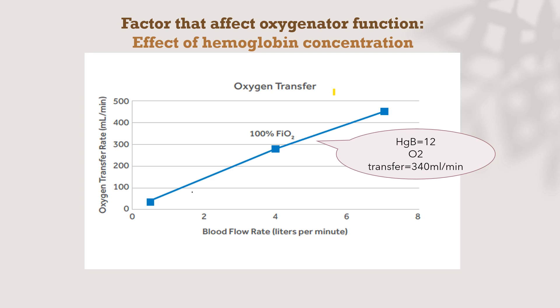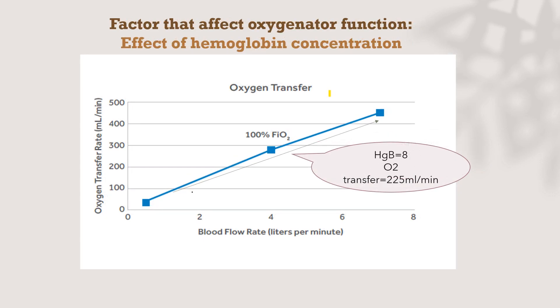Regarding hemoglobin concentration: from this curve, if the patient has a hemoglobin of 12 g/dL, FiO2 100%, and inlet SpO2 of 75%, the oxygen transfer will be 340 mL per minute. But if hemoglobin drops to 8 g/dL with the same flow and same FiO2, the oxygen transfer drops to 225 mL per minute. Hemoglobin plays a very important role in arterial oxygen content through the equation: hemoglobin × 1.34 × SpO2. So hemoglobin is a very important component in oxygen content and oxygen transfer.